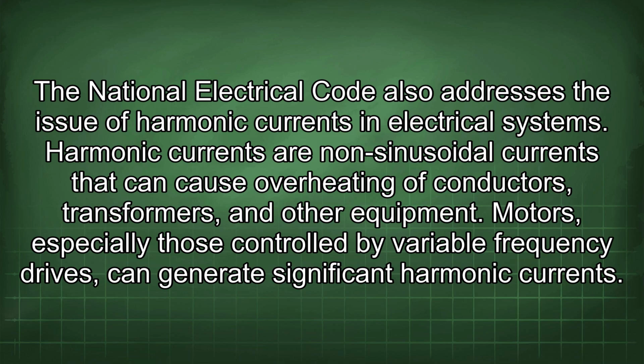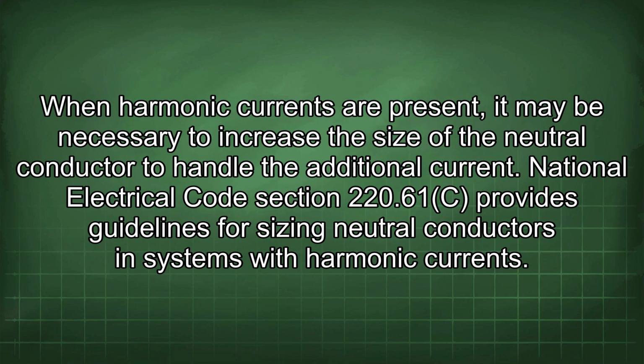The National Electrical Code also addresses the issue of harmonic currents in electrical systems. Harmonic currents are non-sinusoidal currents that can cause overheating of conductors, transformers, and other equipment. Motors, especially those controlled by variable frequency drives, can generate significant harmonic currents. When harmonic currents are present, it may be necessary to increase the size of the neutral conductor to handle the additional current. National Electrical Code Section 220.61(C) provides guidelines for sizing neutral conductors in systems with harmonic currents.